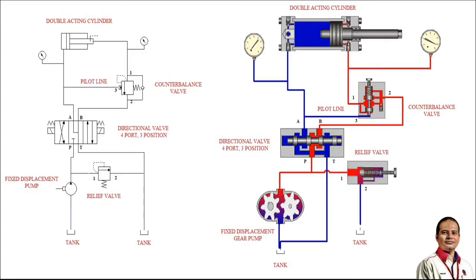So I'll advance it a frame. If I go back a frame, you can see this poppet. It's blocking the path right there. But now, if I advance it a frame, you can see it move. See? Back and forward. And now if I keep advancing, what's going to happen? Well, our relief valve closed off again, and now our cylinder is going to retract. So this is what I would call a steady state position. I'm advancing it frame by frame, but on our counterbalance valves, the flow path is open from 2 to 1 via that check, and oil in the piston end of the cylinder has an easy path back to tank.